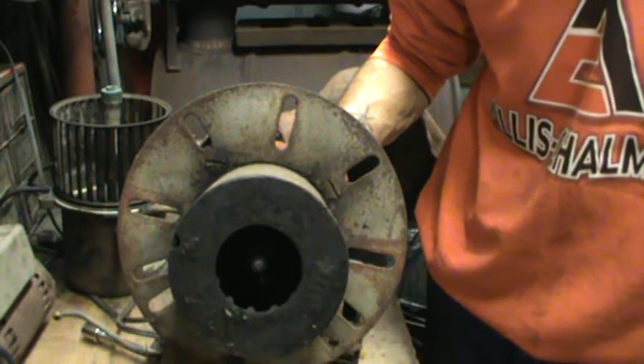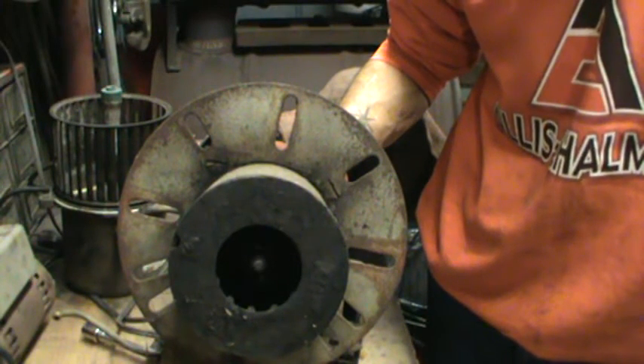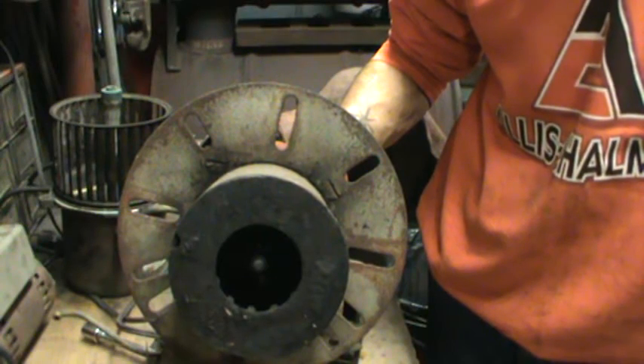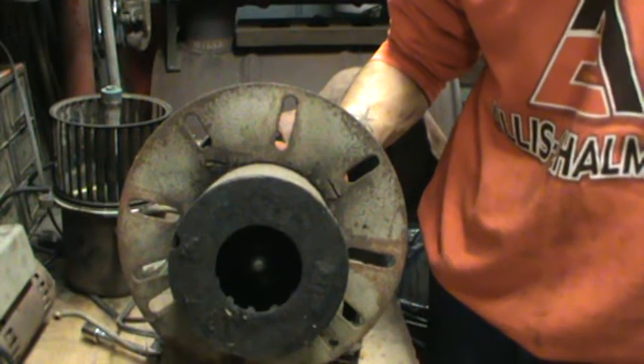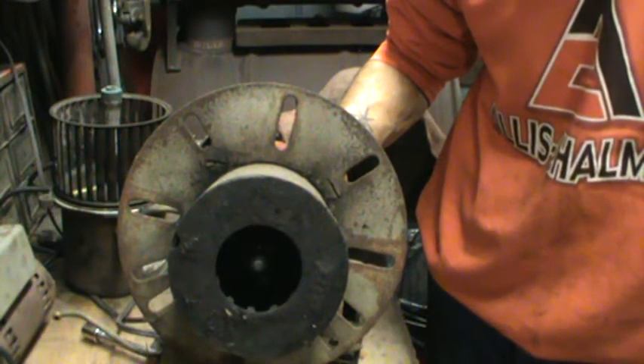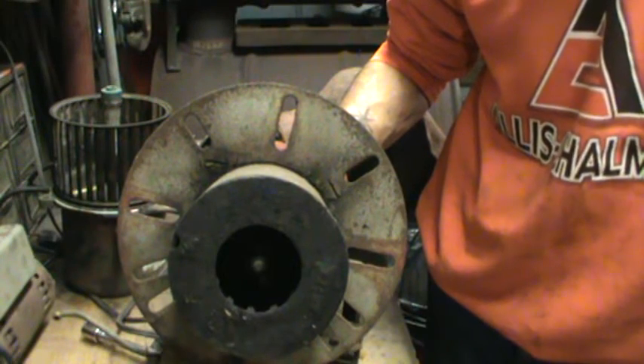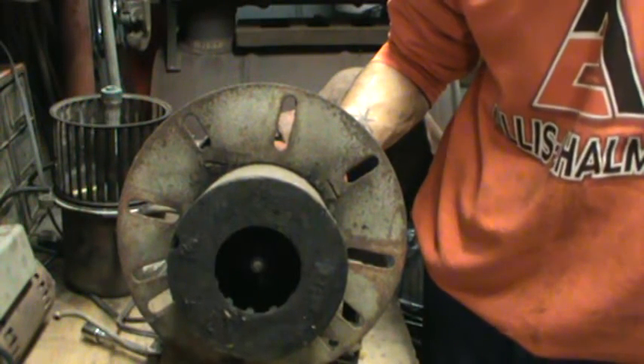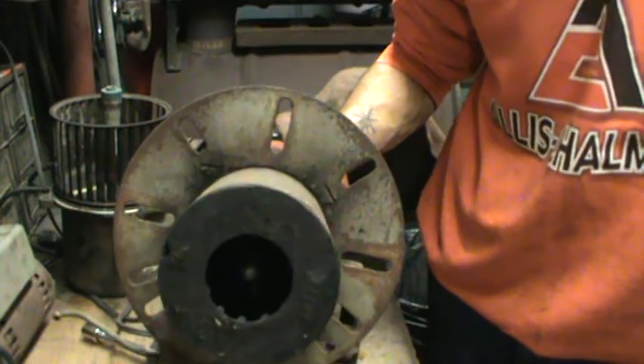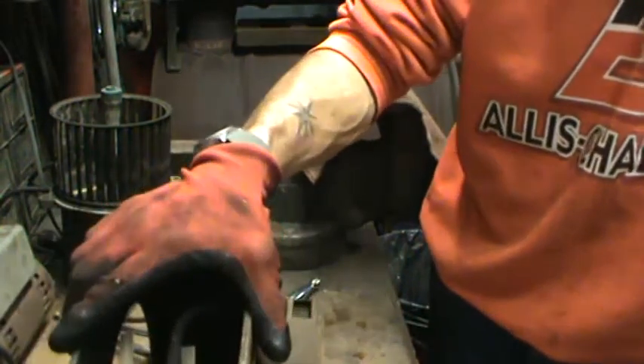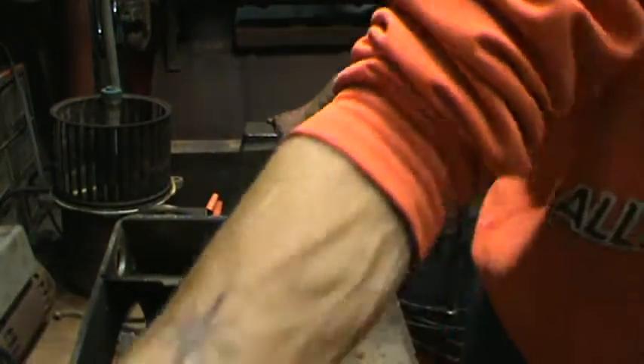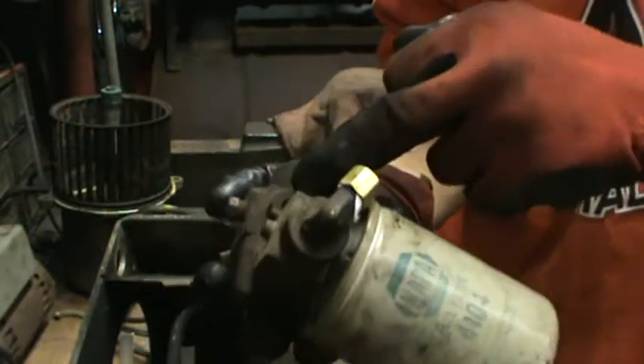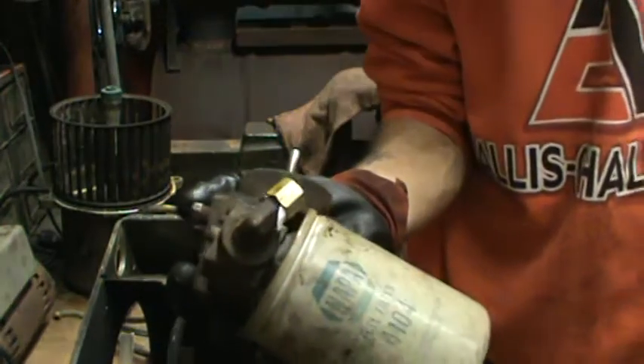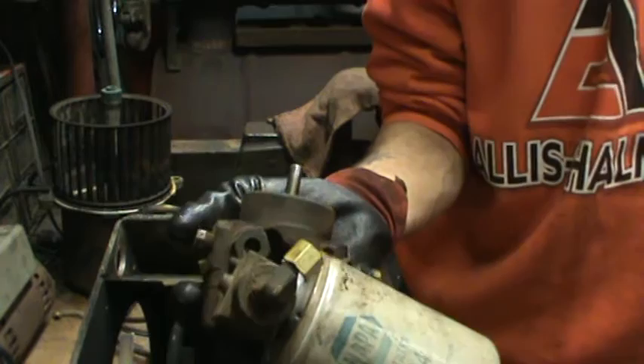So, you know, you can have a 0.75 gallon per hour or 0.70 gallon per hour with a 60 degree, 45 degree, 80 degree, depending on what the size of your burn chamber is and what kind of burn you're looking for. And then, of course, the pump itself is adjustable. This particular one, the adjustment screw is right here, and you can adjust. These are supposed to be set at 100 psi.